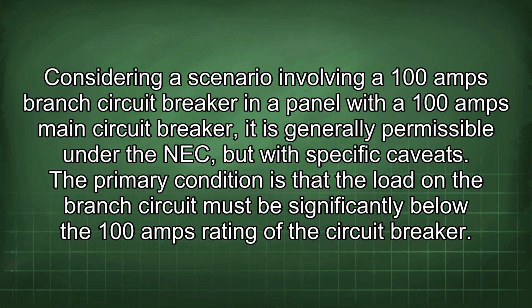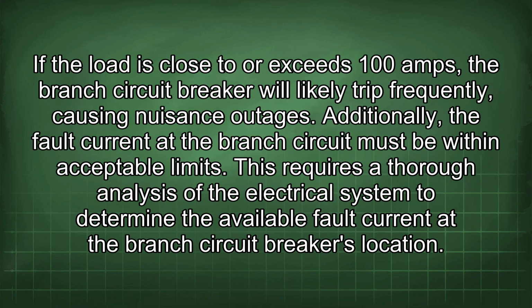Considering a scenario involving a 100 amp branch circuit breaker in a panel with a 100 amp main circuit breaker, it is generally permissible under the NEC, but with specific caveats. The primary condition is that the load on the branch circuit must be significantly below the 100 amp rating of the circuit breaker. If the load is close to or exceeds 100 amps, the branch circuit breaker will likely trip frequently, causing nuisance outages. Additionally, the fault current at the branch circuit must be within acceptable limits.